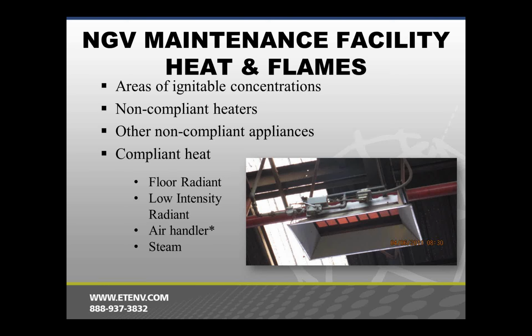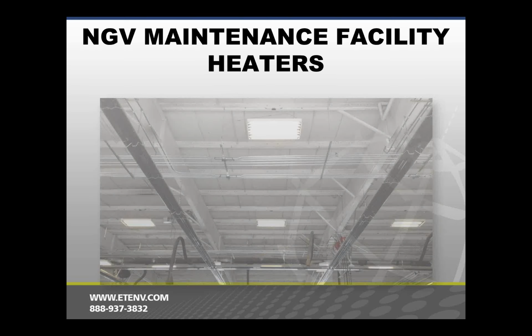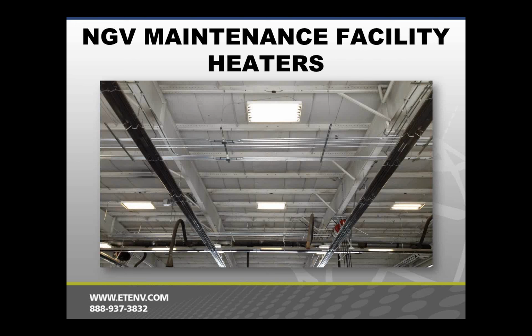So what is compliant heat? One, I was recently in a shop that had floor radiant heat, which was very nice, so there were no heaters to replace. Low intensity radiant heating, it's not uncommon. Many manufacturers, or several manufacturers, make a radiant tube heater that satisfies the requirements for natural gas vehicles. You could also use an air handling unit that would be located such that it wouldn't have burners that are subject to the shop air environment. You couldn't recirculate air back through that unit. Also steam heat, which I've seen one shop that had that scenario. So here's a picture of a shop that we did, and it has the infrared, the low intensity radiant heaters here that are compliant.